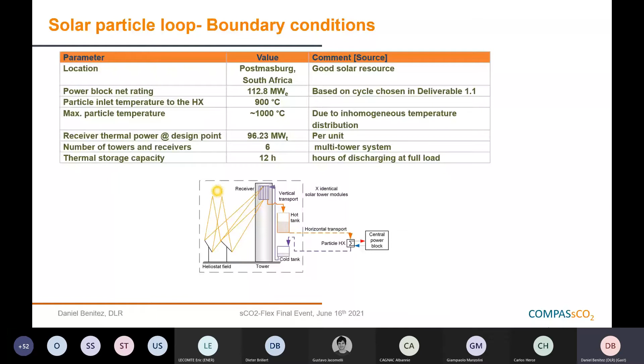For this system, the type of receiver is the so-called CentRec receiver that DLR has been developing for many years, and has a maximum power, let's say around 100 megawatts. So therefore, we need 6 towers. It's a so-called multi-tower system with a large storage of around 12 hours of full load discharge. Then we have done the LCOE optimization of the CSP plant, mainly the heliostat field for the location and for the tower size and for the temperatures obtained and so on.